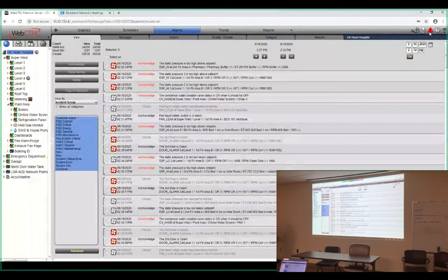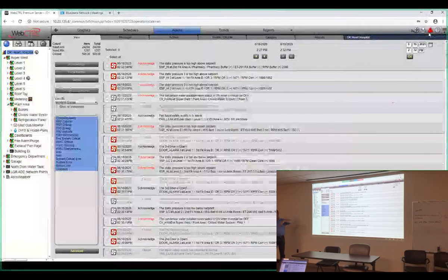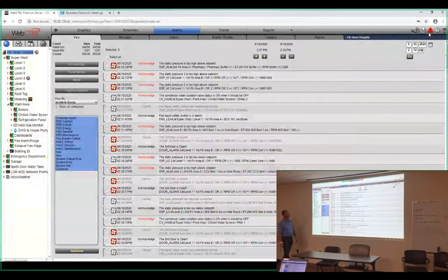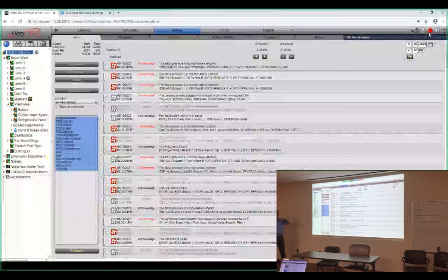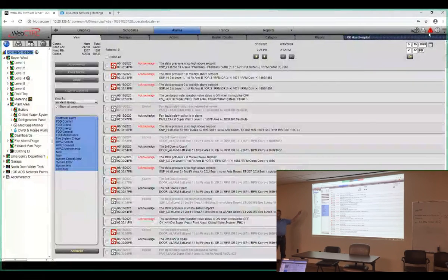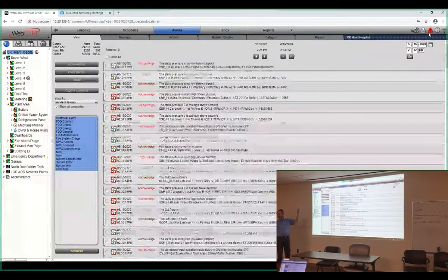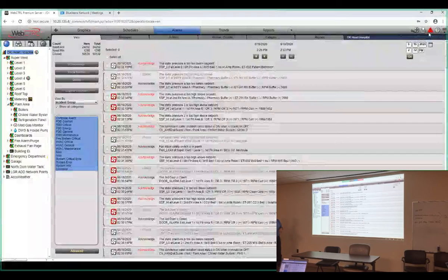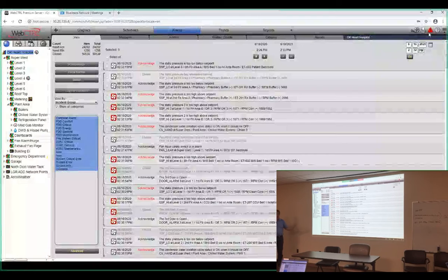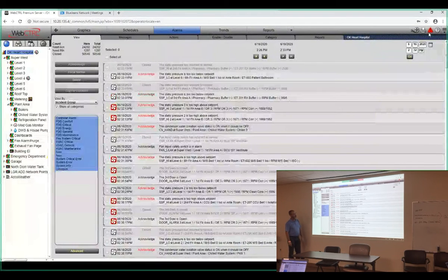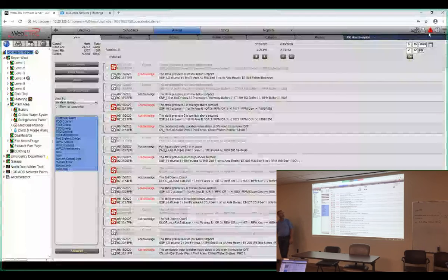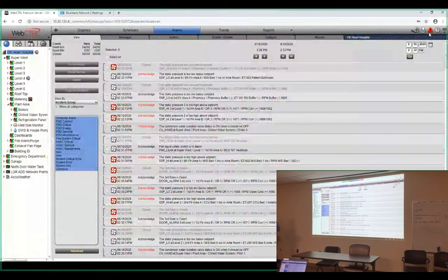So still quite a few alarms coming in. That's what I'll spend probably the rest of this week working on, is seeing what's nuisance and trying to get those to be valid alarms for you. So now that we've got emails going through, I noticed all weekend long in the ED, VAV 113 was alarming about every hour. I backed it off, so I fixed that for you yesterday, and I'll just start doing the same thing through your entire building. Go through alarms, see what's causing the alarm, take care of it. Questions? You don't want 24,000 alarms in a week?